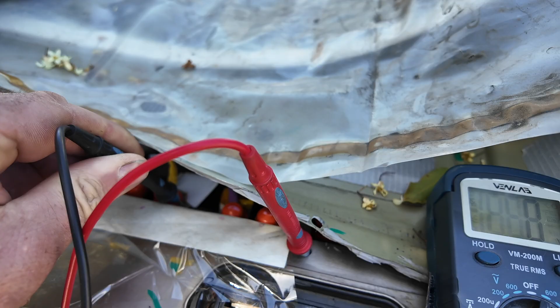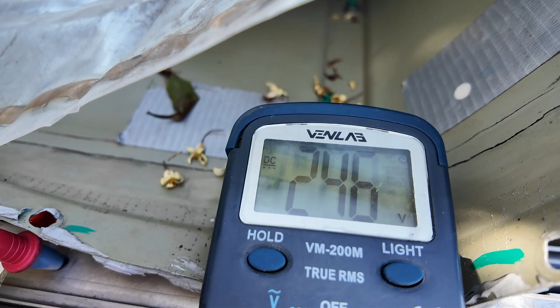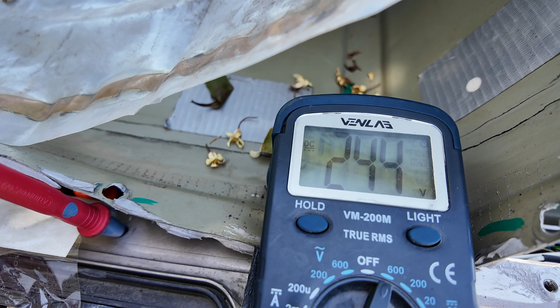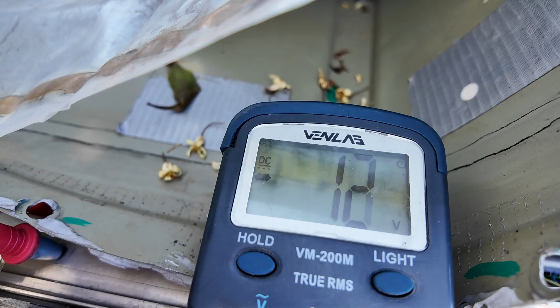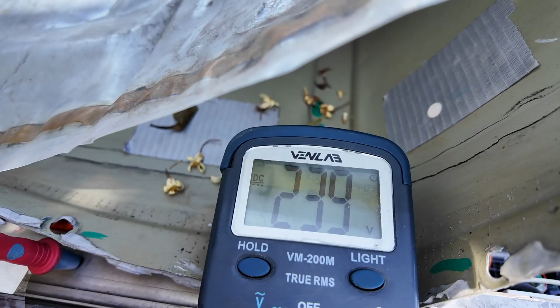So now we're going to measure the voltages one more time, back to the contactors. We still have moisture on the wall of the housing, which indicates the moisture crept up the wall of the pyro fuse housing itself. I need to completely dry this out before continuing. This side has only 12 volts now, and this one still 240, so it lost about 60 volts.